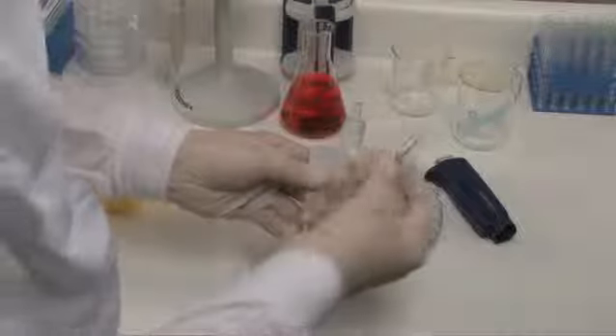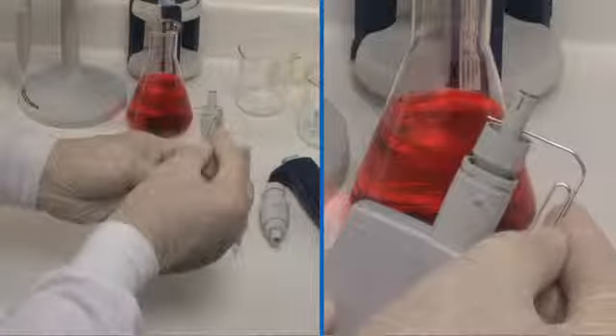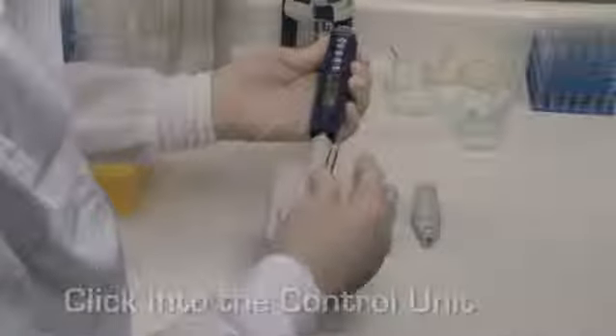Pull out the plunger from the multi-channel volumetric module. Insert paper clip. Insert the rod into the hole and click it into the control unit. Remove the paper clip. Insert the ejector ring with the protruding square on the side and click it in. Pull down and screw in the multi-channel volumetric module. Then screw the ejector ring.